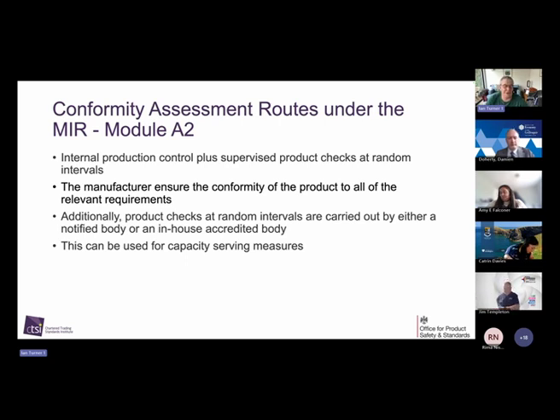The manufacturer must ensure the conformity of the product to all of the relevant requirements. The random checks can be carried out by either a notified body or an in-house accredited body. So you've got these two situations, and it's capacity serving measures. Funny enough, something like this, little aluminium cups. If you look at them when they're made, they're all quite simple. Looking at thimble measures, a bit of tube, you cut the tube up, you put a base in it. You make the first one, you can make the following 10,000 pretty accurately. So they have to take checks. If they've got an in-house accredited body, they can do those checks. Otherwise, the notified body or approved body can come in and do it.